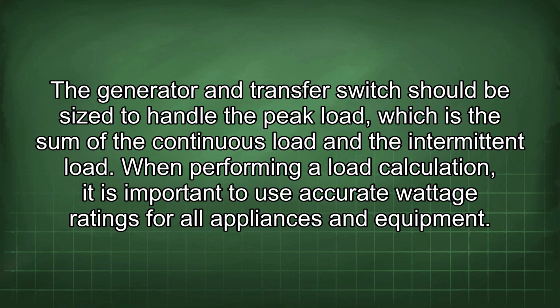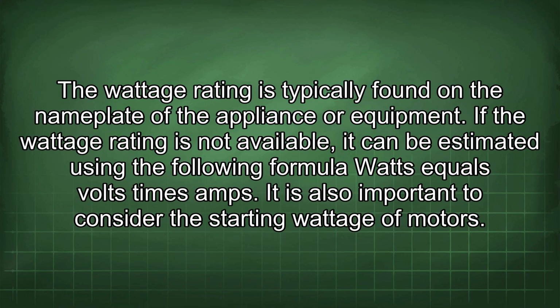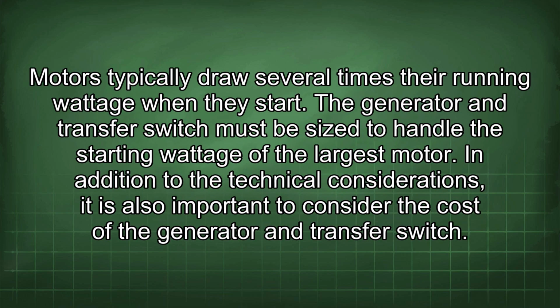When performing a load calculation, it is important to use accurate wattage ratings for all appliances and equipment. The wattage rating is typically found on the nameplate of the appliance or equipment. If the wattage rating is not available, it can be estimated using the following formula: watts equals volts times amps. It is also important to consider the starting wattage of motors. Motors typically draw several times their running wattage when they start. The generator and transfer switch must be sized to handle the starting wattage of the largest motor.